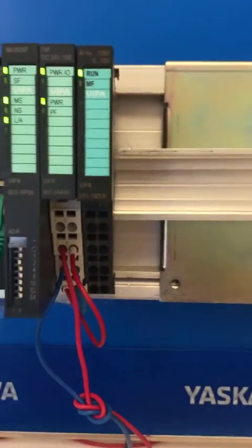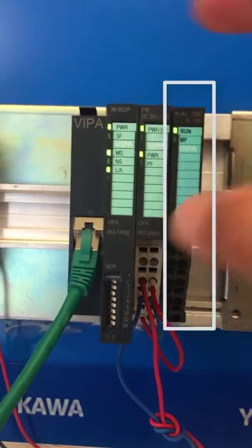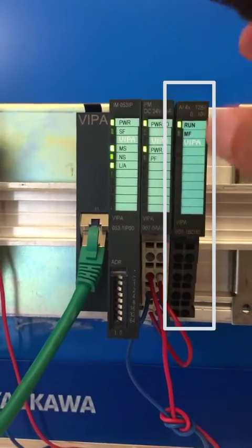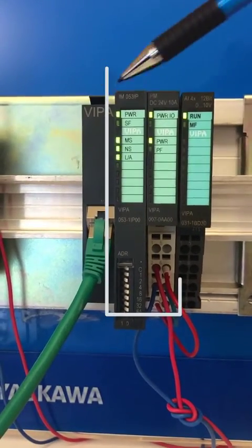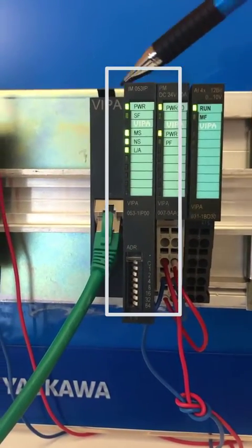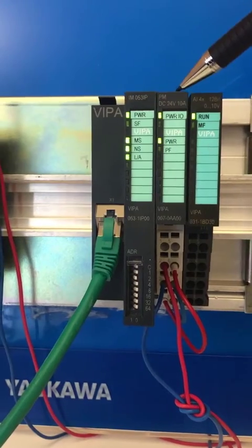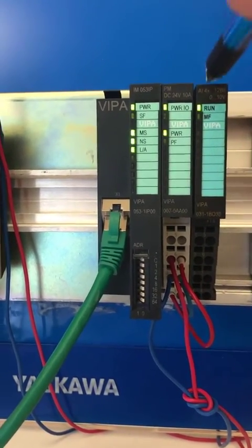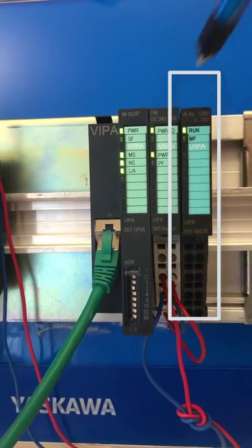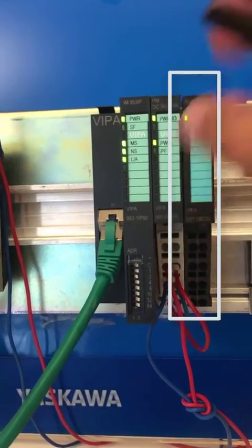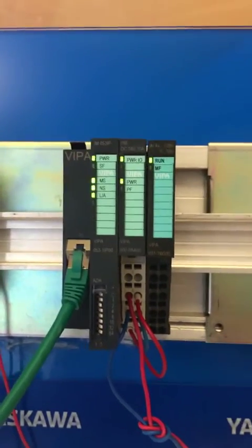So important always to consider in this version, the 00, is that you always need one module on it. If you have the coupler, so what you see here, these two parts, is not enough. You need, mandatory, to have one module linked to the coupler. Only then can you make the change of the address.